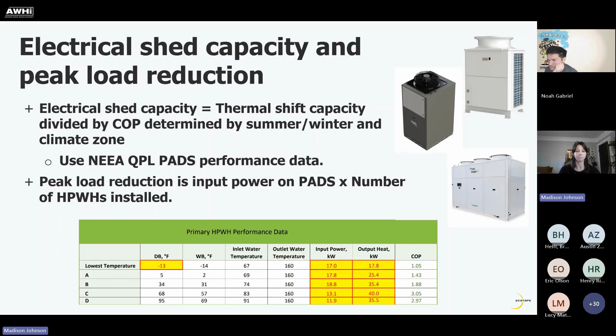After running the single draw test, or using the EcoSizer engine to get thermal shift capacity, we use NEEA's qualified products list performance assessment data sheets to estimate electrical shed capacity. Electrical shed capacity is the thermal shift capacity, or stored energy, divided by the COP. Thermal shift capacity estimates how much electrical energy we can shift outside of a designated peak period, and we compute this for both summer and winter. We also report peak load reduction, which is heat pump input power multiplied by the number of heat pump water heaters installed.